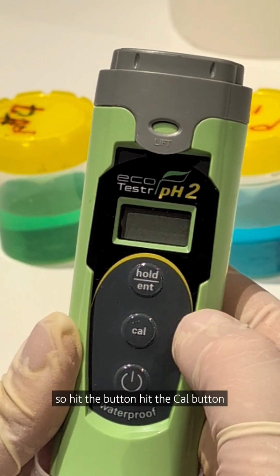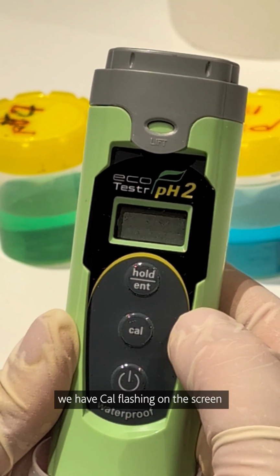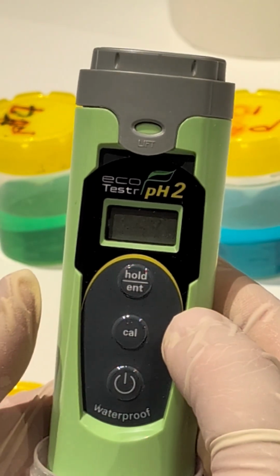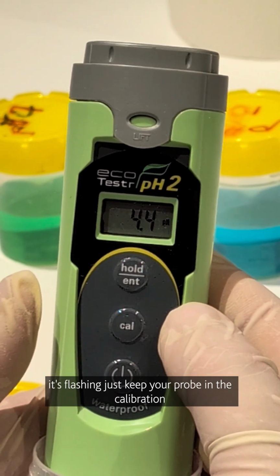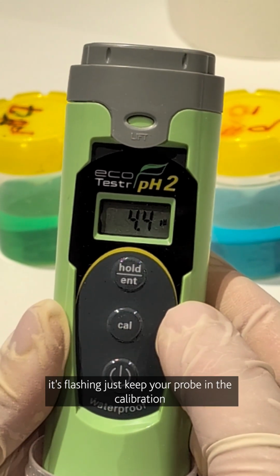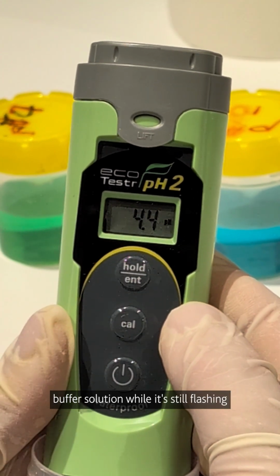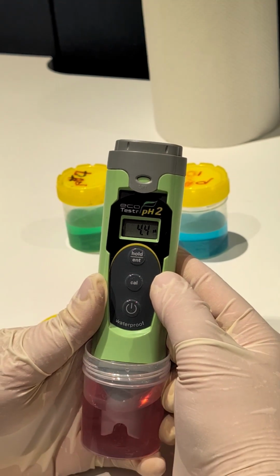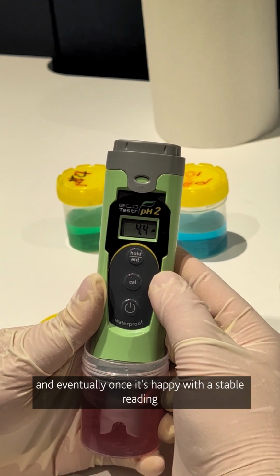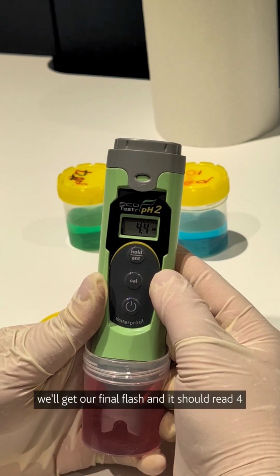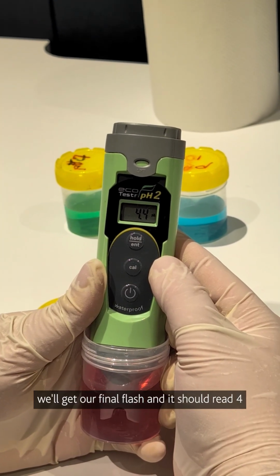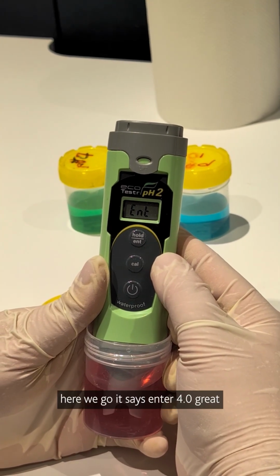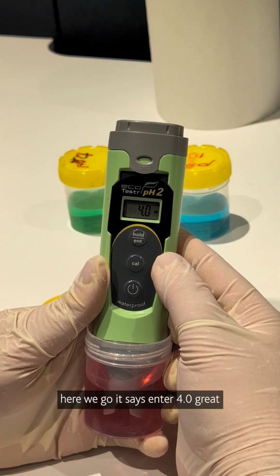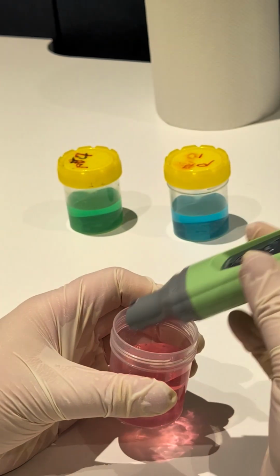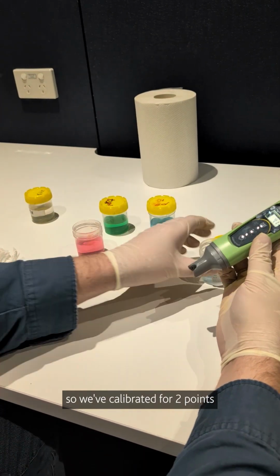So hit the button, hit the cal button. We have cal flashing on the screen. The number it's reading at the moment is flashing. Just keep your probe in the calibration buffer solution while it is still flashing. And eventually, once it's happy with a stable reading, we'll get our final flash, and it should read 4. There we go. It says enter 4.0. Great. So we've calibrated for 2 points.